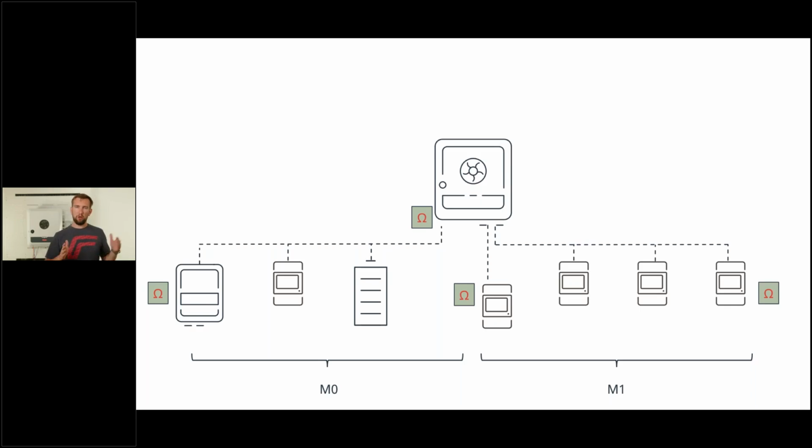We could switch Modbus 0, M0 termination on and have this line on the left-hand side between the Ohmpilot, where we can again use a dip switch to activate the resistance, then include a smart meter, a battery, etc. on the way to the inverter, and terminate that resistance at the inverter again.